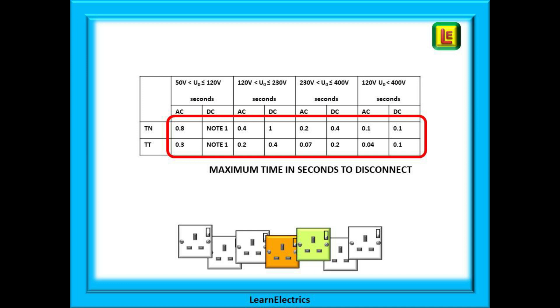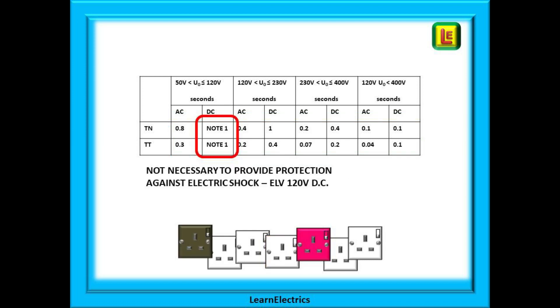The bottom part of the table, shown here circled in red, gives the disconnection time in seconds. Outlined in red on this slide are two entries that tell us to look at note one to this table. Because this is a DC voltage and it is up to 120 volts it falls into voltage band 1, which is extra low voltage and does not require protection against electric shock — at 120 volts DC you are unlikely to receive a fatal electric shock.